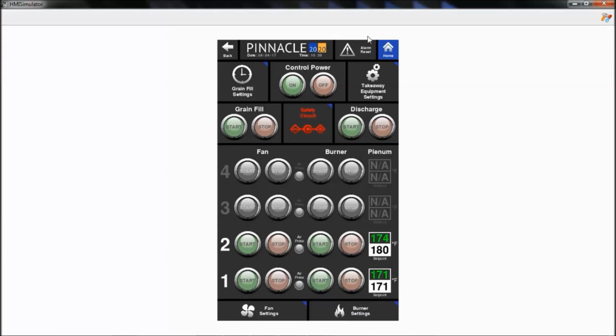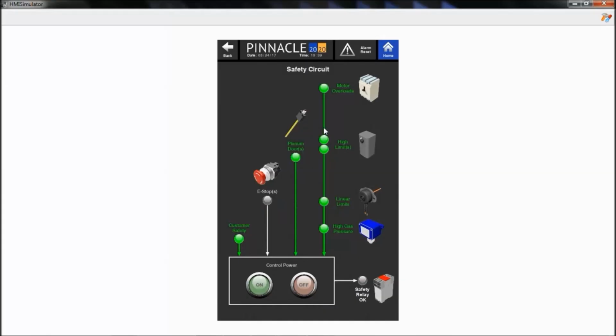We'll also notice in this event there's no active alarms because perhaps somebody came over and acknowledged the alarm already, but they never actually fixed the problem. So this is a scenario that can happen and sometimes can be hard to identify. If you come into a situation like this, we see that the safety circuit button is illuminating red. If we click there, it brings us to this page. And we can at a glance see that everything's illuminated except for the E-stops.